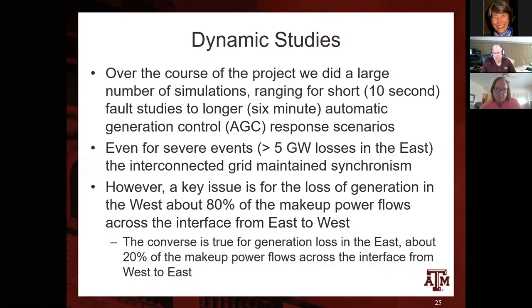Some simulations were much longer—we might run a 6-minute simulation to make sure we didn't have any low frequency oscillations going on in the system, and that we had a reasonable response for the automatic generation control. So sometimes we'd run these out for up to 6 minutes. What we found is that even in severe events, and we did some really severe events, the grids maintain synchronism.